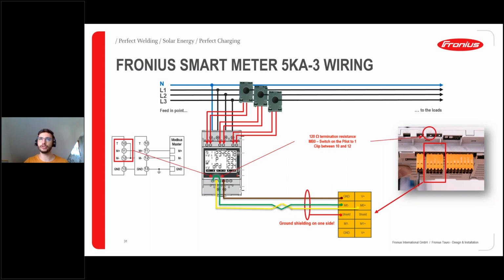And on the inverter, on top here, above the orange plug, we have a small dip switch, which we need to set to on, or the 1 position. And then also here we have set the 120 ohm resistor. So these are 3 very important topics. Please always remember them to have the correct and the best available data communication possible.